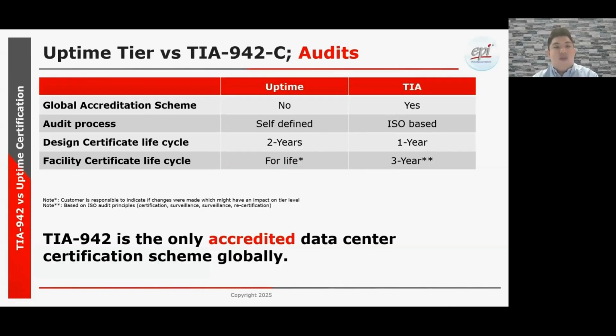So audit process: uptime is self-defined, TIA is solely following ISO. For the design certification life cycle, uptime certificate expires every 2 years, and TIA design certification expires in a year. But if you've successfully obtained the DCDV design certification from TIA and the build requires more than a year, you can write back to us stating the construction is still ongoing, and it can be extended.